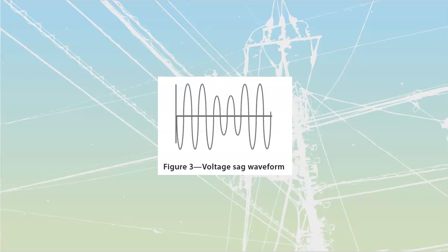Voltage sags oftentimes are going to be significant enough, because it's just a rapid drop in voltage, usually due to massive motors starting up, that we're going to kick out a lot of our computerized systems. They're designed with a safety so that if the voltage gets too low, they kick off, so they just respond and shut themselves off. But VFDs and adjustable speed drives are also designed with the same thing. They're going to shut down because they don't want to have a low DC bus link.